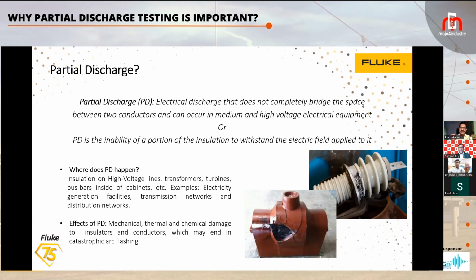In fact, partial discharge is the electrical discharge that is not completely bridging the gap between two conductors. If there is a kind of discharge happening, that is what you call partial discharge. It can occur at low voltages also, but usually partial discharge occurs above 3 kV. Any system working above 3 kV is expected to have partial discharge. In other words, PD is the inability of a portion of the insulation to withstand the electrical field applied to it. This is a very interesting subject, because in electrical systems, the insulation material plays a major role. Every equipment is designed with conductors and insulation, right? They have to work in tandem, then the machines will work. The moment there is a failure or weakness in the insulation, partial discharge pops up.